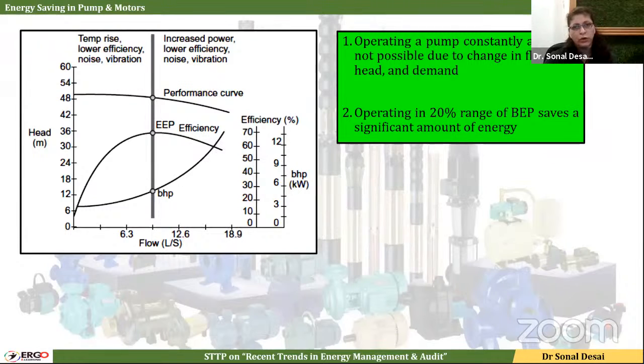One example, if I give, say for example, we are running a pump for a cooling tower requirement. The cooling tower requires water, which the pump supplies, but that water level will not be the same during all weathers, or during daytime as well as night time. We know that it is based on the temperature of the surrounding air. So when the surrounding temperature drops, the flow rate of water will also drop. So over there, flow rate variation will occur, and in that case, we cannot make the pump operate at a continuous flow rate. So whenever such a requirement is there, if we shift the pump operation point, it will hamper the efficiency.